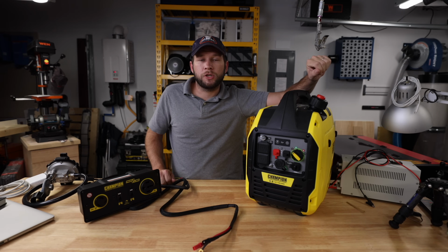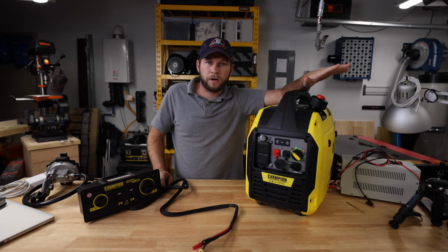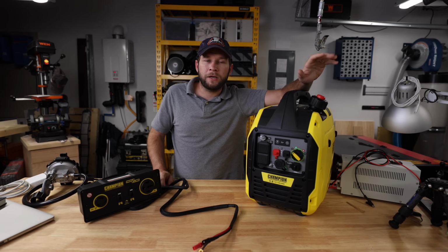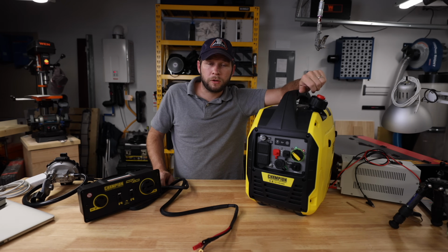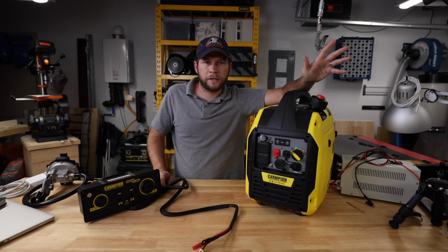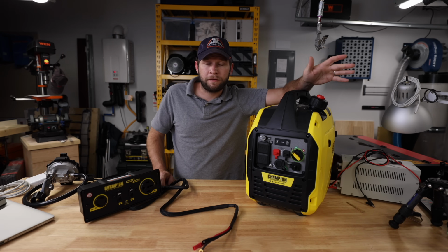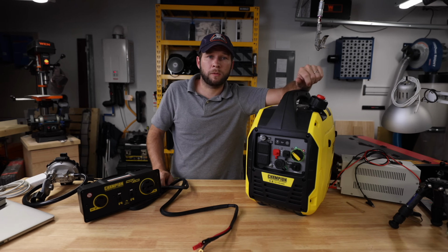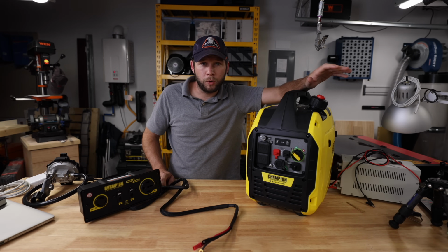Now, this brings us to all of the different variations. There are a zillion different ways of connecting these into your house, and so many different kinds of generators that it's unreal. Westinghouse has a couple of new generators that are really nice, a 12,000 I think and a 15,000 watt standard generator. These just have a voltage regulator, nothing special. They're not inverter generators, and yet they maintain under a 5% total harmonic distortion on the power. So these are effectively whole home backup generators, but they can move.